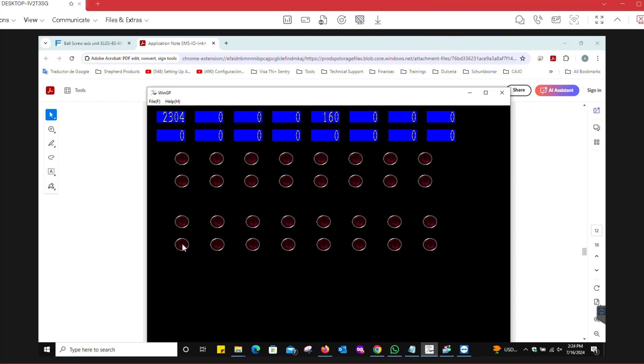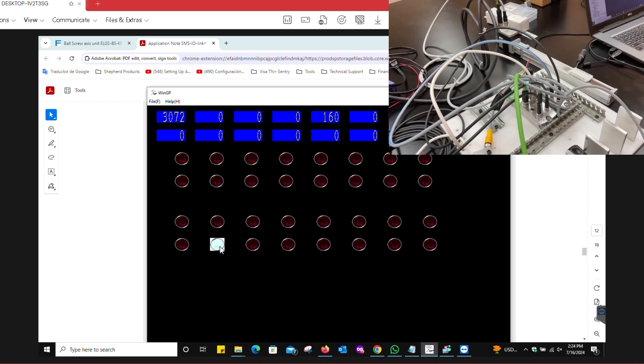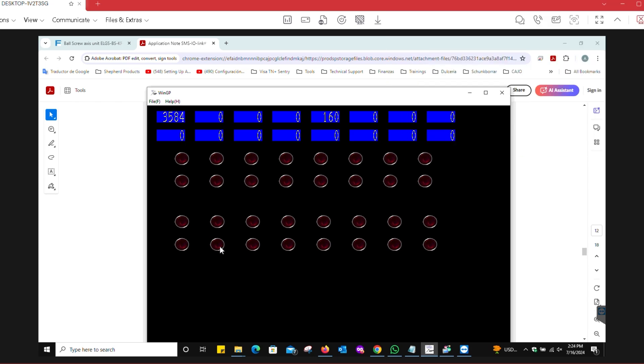If I want to move it out, this is going to be bit nine. Now it's moving out. With these two bits, you're controlling the actuator and you're getting the feedback here: 2560 and 2304.